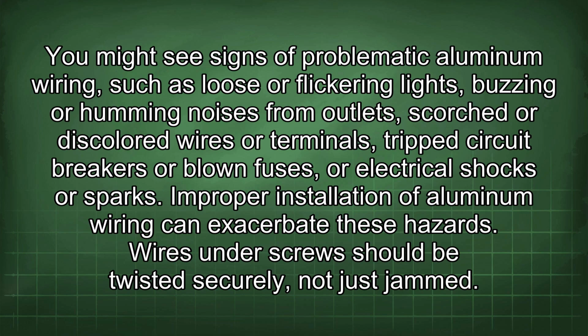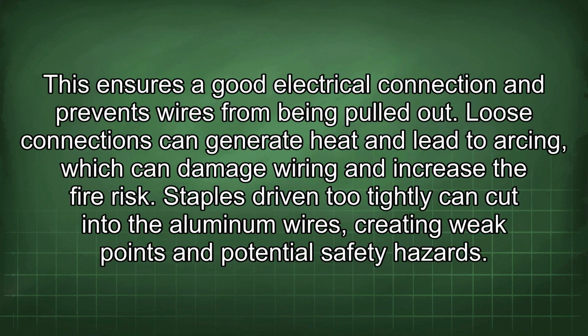Improper installation of aluminum wiring can exacerbate these hazards. Wires under screws should be twisted securely, not just jammed. This ensures a good electrical connection and prevents wires from being pulled out. Loose connections can generate heat and lead to arcing, which can damage wiring and increase the fire risk. Staples driven too tightly can cut into the aluminum wires, creating weak points and potential safety hazards.